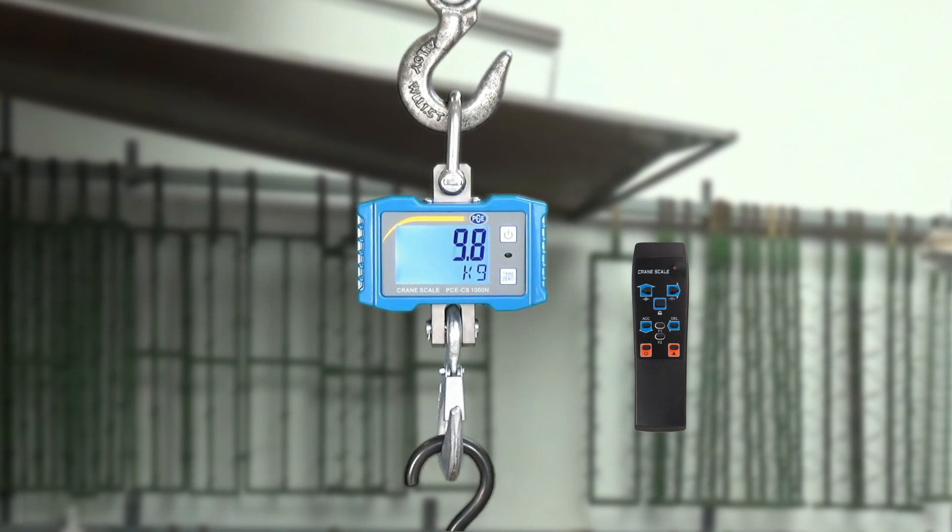When I now unload the crane scale and load it with 10 kilos, I can through the summing of the load, ACC on the remote press. ACC is shown in display. I can let show the whole mass. Before it was 5 kilo, plus 10, or 15.